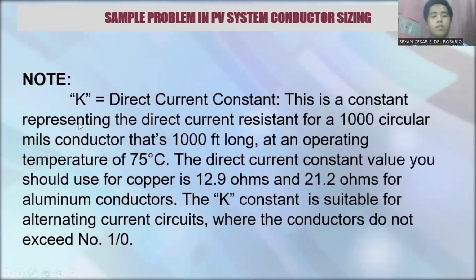Next, ito yung K na sinabi ko. K equals to direct current constant. This is a constant representing the direct current resistance for a 1,000 circular mils conductor that's 1,000 feet long at an operating temperature of 75 degrees Celsius. The direct current constant value you should use for copper is 12.9 ohms. Since copper yung ginamit natin, 12.9 ohms yung kinuha nating value.